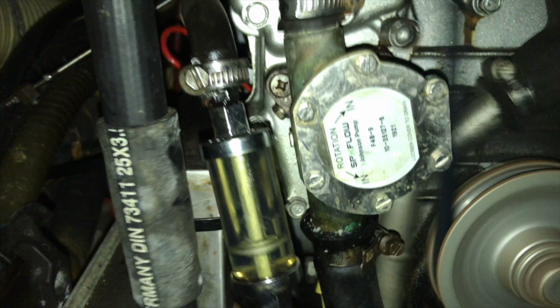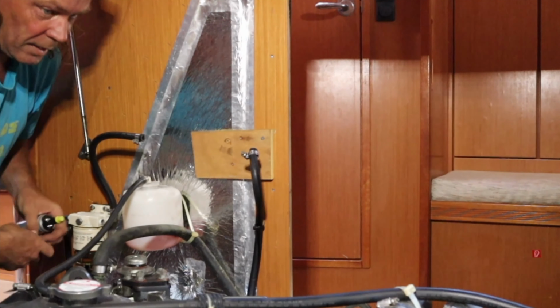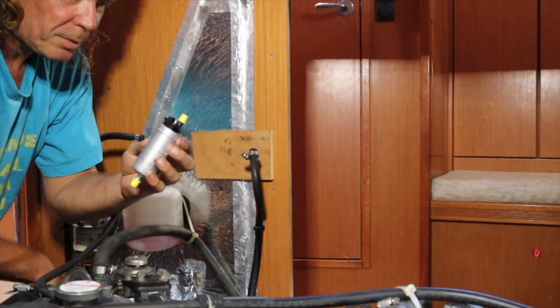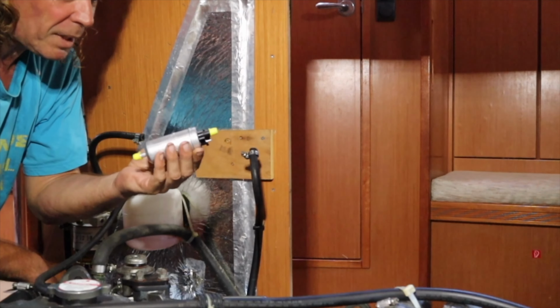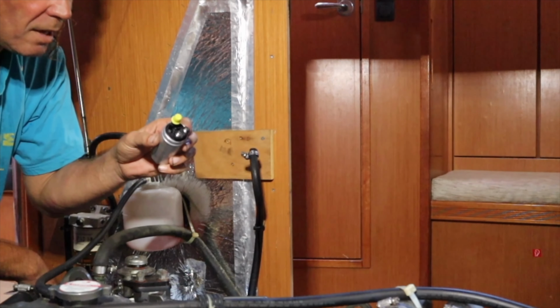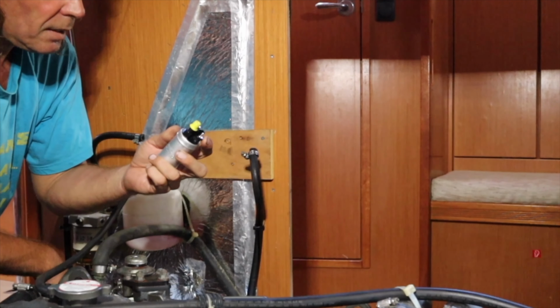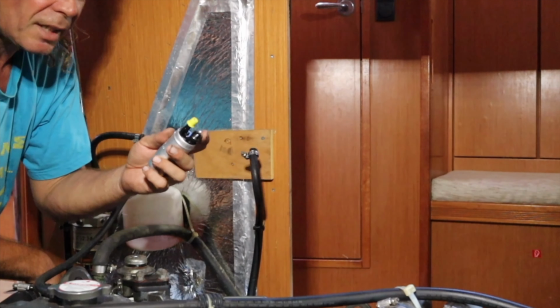After changing filters or the feeding pump, jump wiring the feeding pump will save you time as well. You only need a cable from the positive on your battery to the positive terminal on the pump. Then you will hear the fan start and also the feeding pump sending diesel through the line.